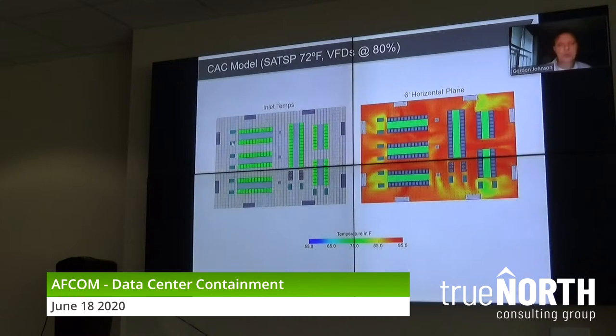All CRAH units have variable frequency drives, or variable speed drives. And please don't worry, I know there's a great lunch waiting; I'm coming down the 5-minute home stretch right now. Your CRAH units are running at 100%. Let's knock those speeds down to 80%. If you look on the left, you still have inlet temperatures of 72, 73, maybe 74, maybe getting to 75. That's very good.